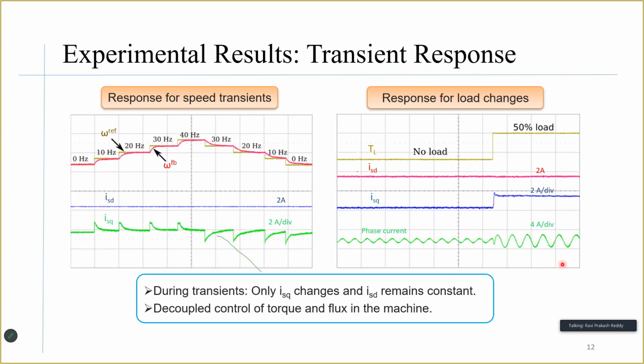Similarly, we also carried out the experiment by loading the machine from no load to 50% load, and we see that during this loading condition, again only the Q-axis component of current, which is responsible for the torque in the machine, responds to the changes in the load torque, and therefore the D-axis component of current is constant, while the Q-axis component varies. Therefore, the phase current also jumps to a higher value to meet the increased load demand. So we have the decoupled control between the torque and flux in the machine retained in the proposed speed control method, as it represents a vector control technique.